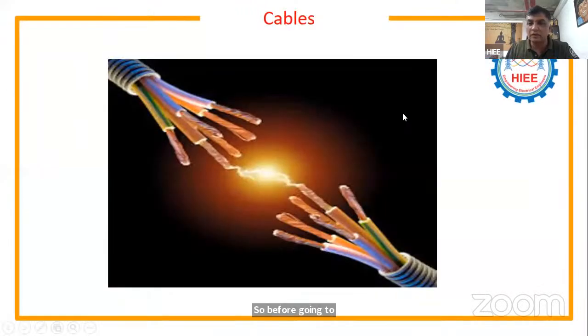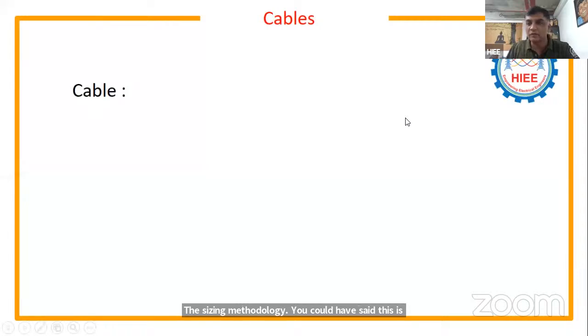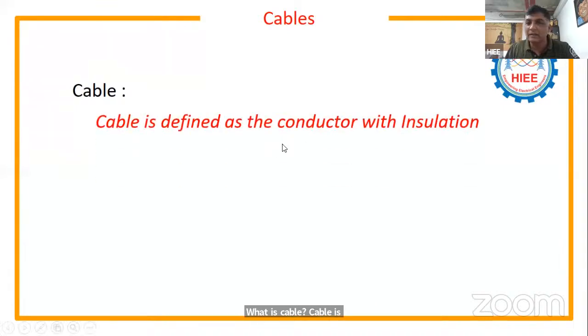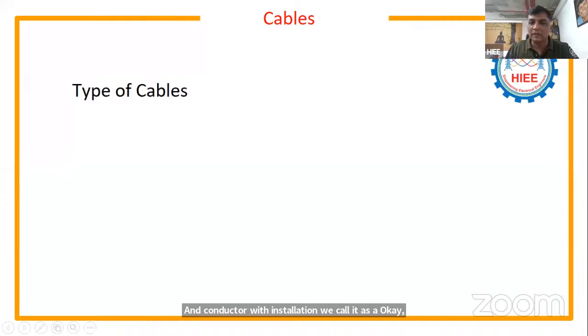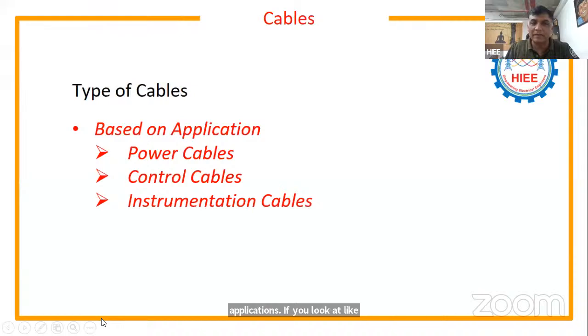the sizing methodology, first you should know what a cable is. A cable is defined as a conductor with insulation. With a bare conductor, generally we use bare conductors for transmission line applications. And a conductor with insulation, we call it a cable. Generally there are multiple applications of the cable. Based on applications, we have power cables, control cables, and instrumentation cables. These are the three types of cables we use for industrial applications.